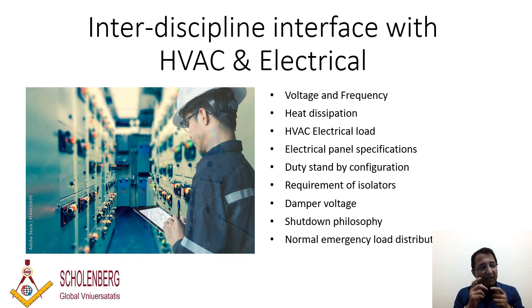Second is heat dissipation. This is not in your hand - you have to get inputs from electrical, because electrical is where the motors and electrical panels are, from which heat is dissipated. Apart from human heat, they also need to tell you what kind of lighting is being used - LED, incandescent, or whatever. Based on that, heat dissipation values come in, as long as motors and electrical panels are considered. There are certain thumb rules I'll tell you later if they don't give the values, but you should always push for these values because if they don't give them, you'll be in trouble.